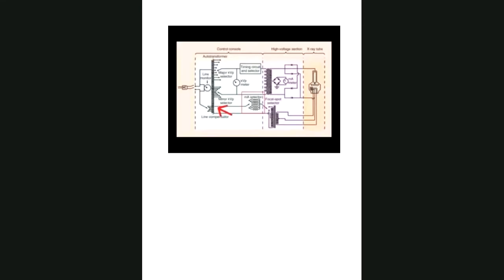Well, the high voltage transformer is on the high voltage side. So the primary side of it, and if you look, let me flip back real quick so I can show you. Here, you see how in Bushong's drawing, he puts it all so both transformers end up in the high voltage section, and that's important to recognize because they both deal with exceedingly high voltage or current.